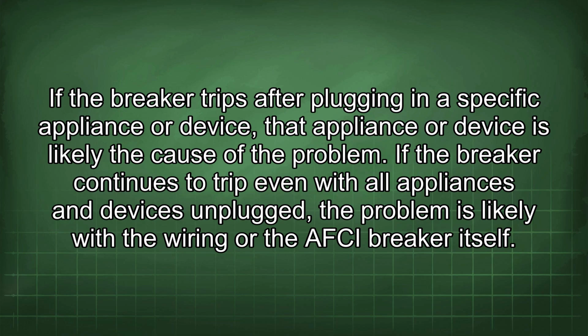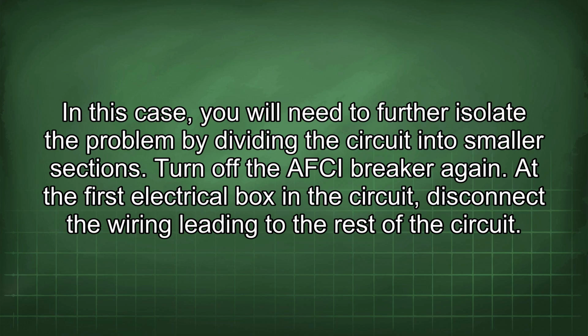of the problem. If the breaker continues to trip even with all appliances and devices unplugged, the problem is likely with the wiring or the AFCI breaker itself. In this case, you will need to further isolate the problem by dividing the circuit into smaller sections. Turn off the AFCI breaker again. At the first electrical box in the circuit, disconnect the wiring leading to the rest of the circuit.